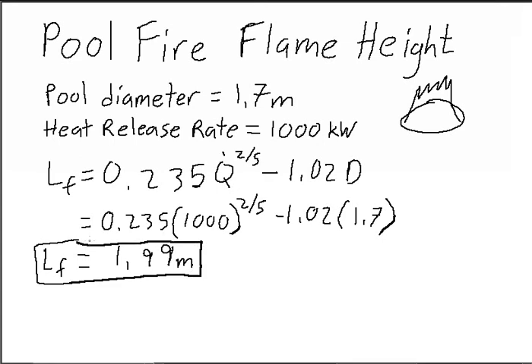Now, in this equation, your heat release rate term, this Q dot, is kind of the hard one to come up with or estimate if you don't have your fire under some kind of hood with oxygen calorimetry hooked up, or something like that.